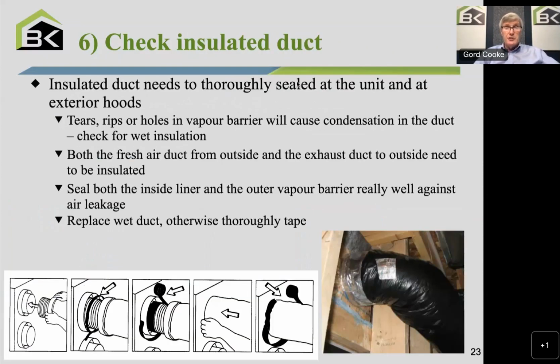And then because you're there, assuming the community office is doing the maintenance, it is a good time to check the insulated ducts. You may recall there are two insulated ducts. The fresh air from outside is cold, so I need to insulate that duct. The exhaust air has come through the heat recovery core, so that exhaust air is also cold, so it needs to be insulated. And what you want to make sure is that the insulation, specifically the outer jacket, in this case the black plastic jacket, hasn't been ripped or torn.